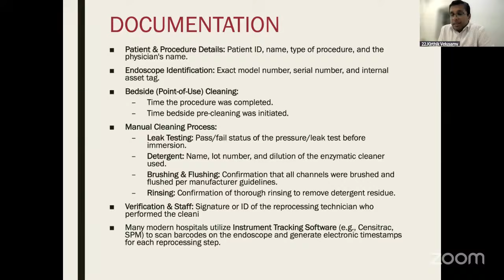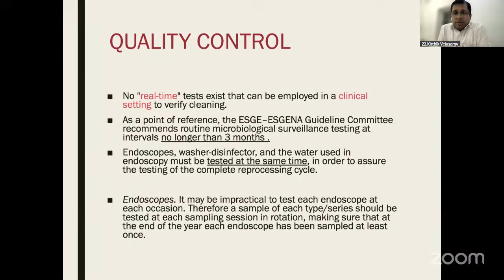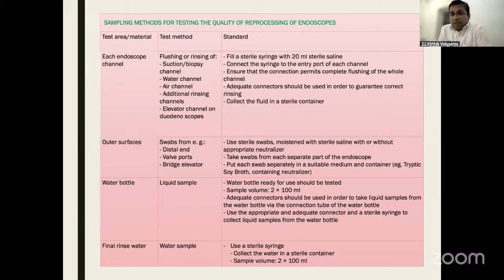Regarding quality control, any system should have quality control, otherwise the whole thing will fail. There is no real-time test in a clinical setting. As a minimum, we recommend biological surveillance every 3 months. Endoscopes and the RO water used in endoscopy should be tested at the same time. For the endoscope channel, we take a 20 ml syringe of sterile saline, flush it, collect it in a container and send it to microbiology. For water, we take 2 samples with a sterile syringe, put them in a sterile container, and send them to microbiology for incubation to look for any growth of organisms.